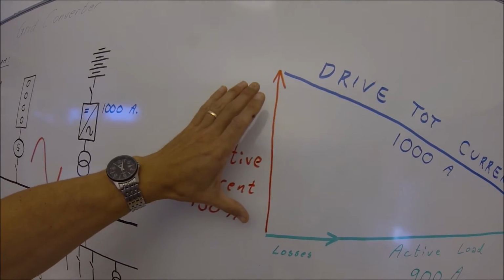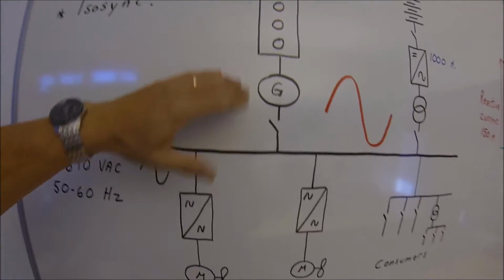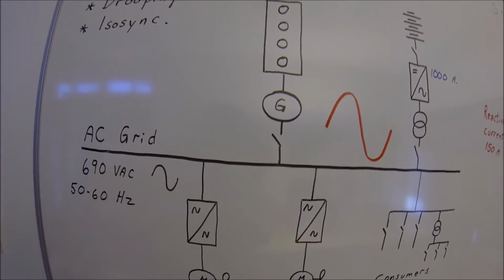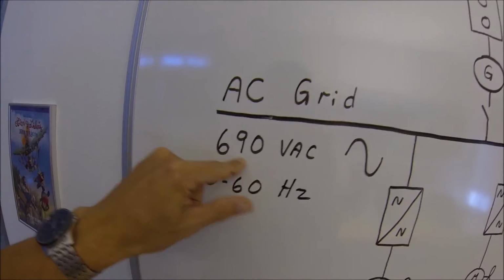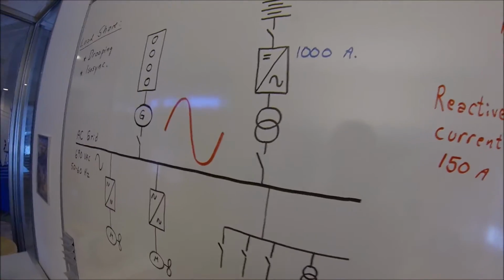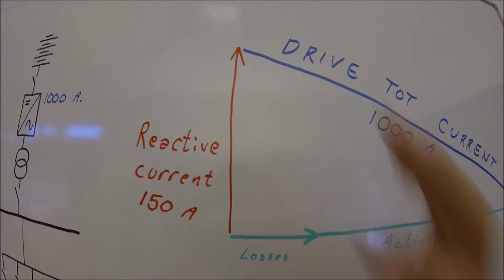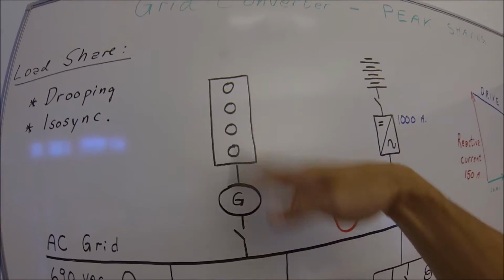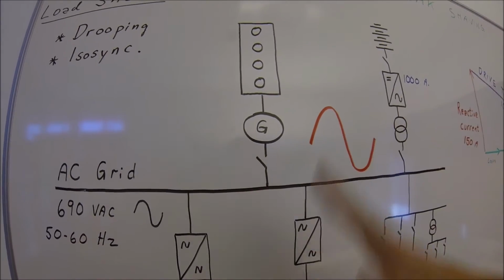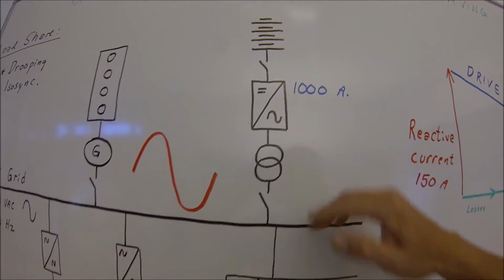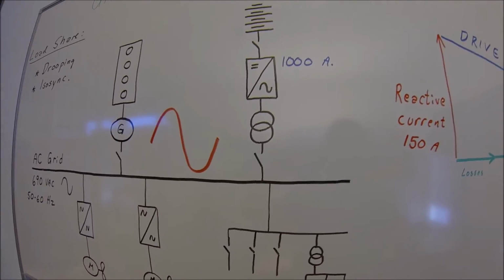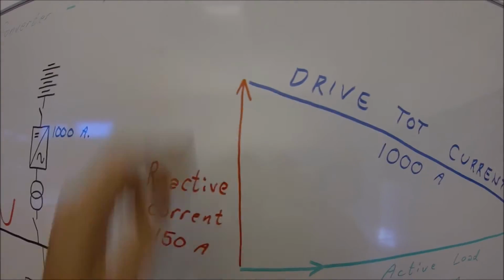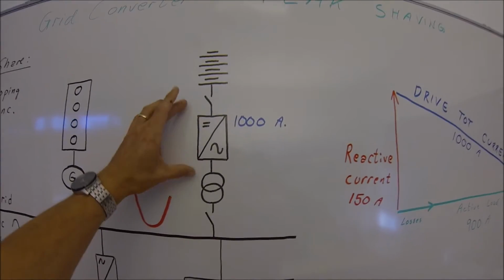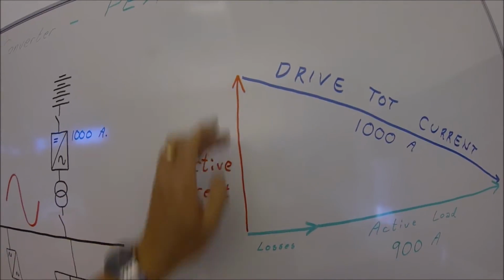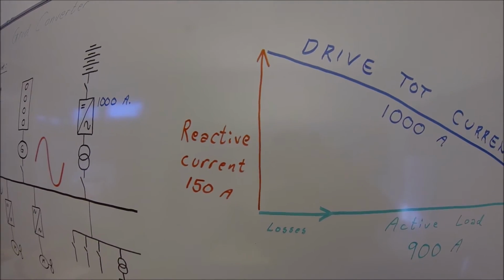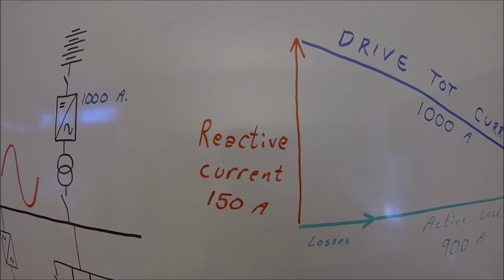When is the reactive current big and when is it small? Well, if you have a ship with a high quality, high precision automatic voltage regulator for the diesel generators, then the voltage will be quite stable. Then our drive doesn't need to compensate much for reactive currents, and the reactive current will be low. However, if it's a ship with not so good precision in the voltage control, where the 690 keeps going all over the place, then the drive needs to follow these voltage changes, and there will be a reactive current going on, and this reactive current will be bigger. So make sure that the dimensioning of the grid also has the margin for handling the reactive current. The reactive current on ships could be anything between 2% and 12%, we have seen in practical life.